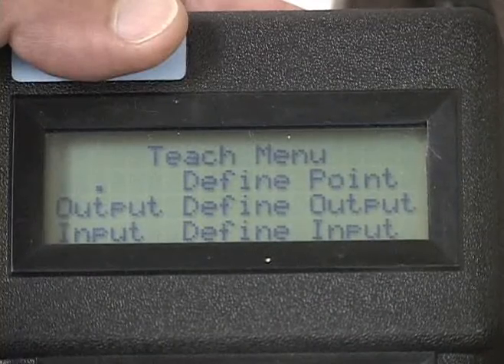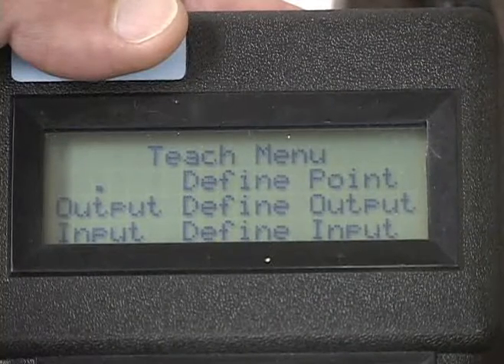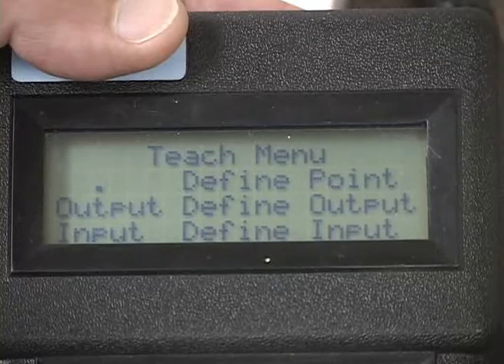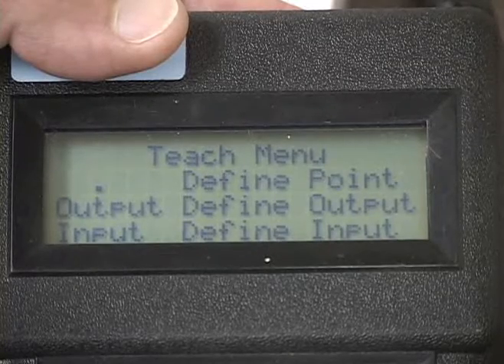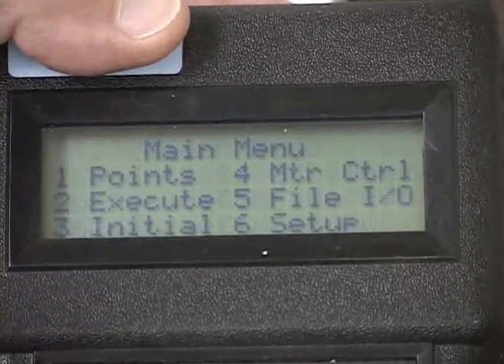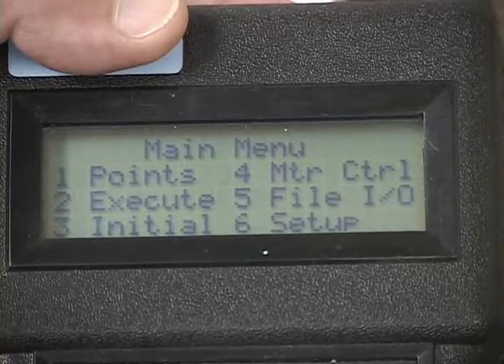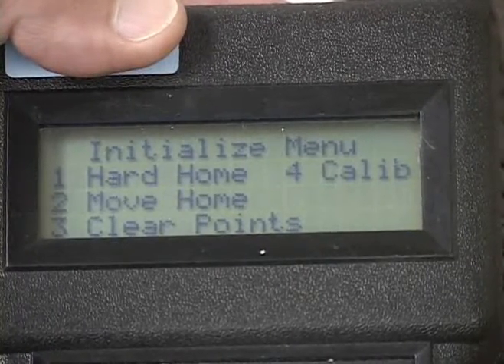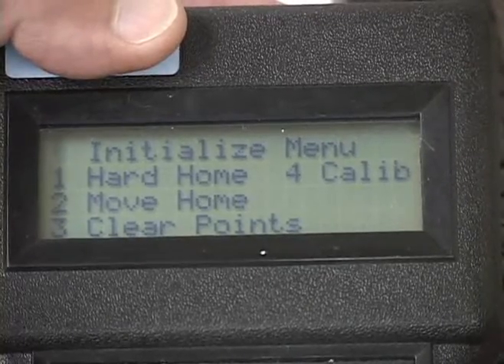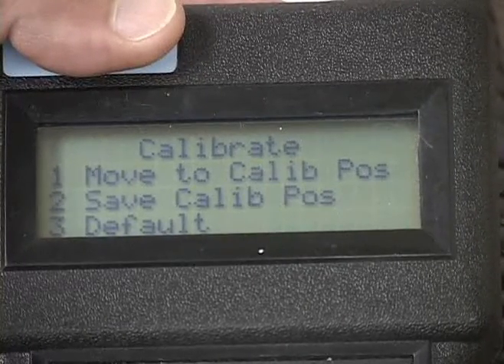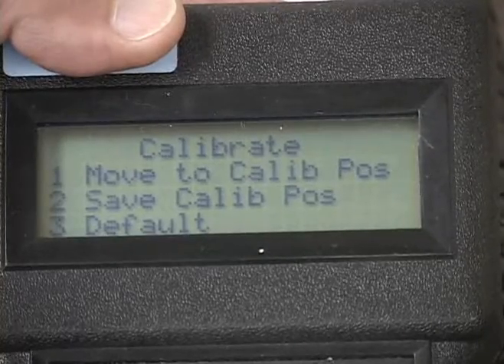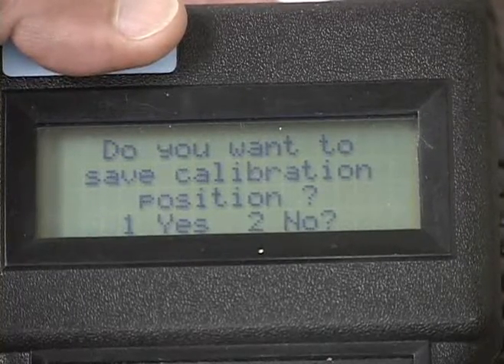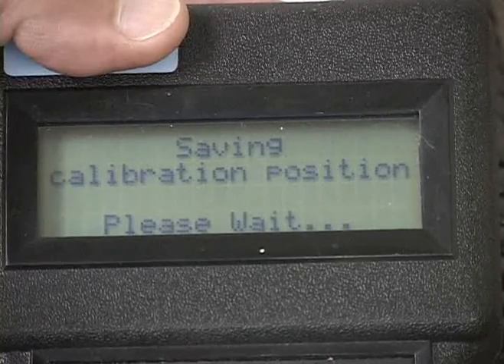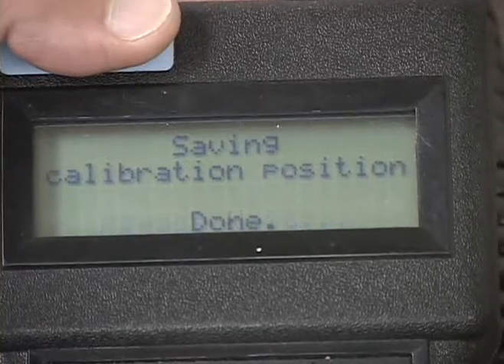Save the calibration position by using the following steps. On the teach pendant, return to the main menu by pressing Escape or Main Menu. Select 3, Initial. From the Initialize menu, select 4, Calibrate. From the Calibrate menu, select 2, Save Calibration Position, then press 1 to save your calibration position. This forces the robot to perform a hard home.